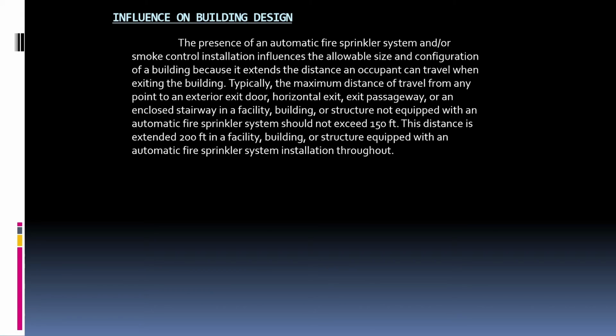The next one is influence on building design. The presence of an automatic fire sprinkler system or smoke control installation influences the allowable size and configuration of a building because it extends the distance an occupant can travel when exiting the building. Typically, the maximum distance of travel from any point to an exterior exit door, horizontal exit, exit passageway, or an enclosed stairway in a facility, building, or structure not equipped with an automatic fire sprinkler system should not exceed 150 feet. This distance is extended to 200 feet in a facility, building, or structure equipped with an automatic fire sprinkler system installation throughout.